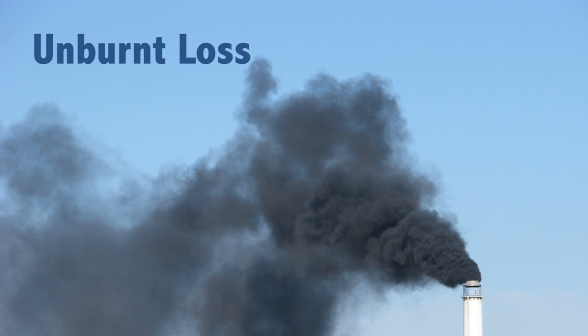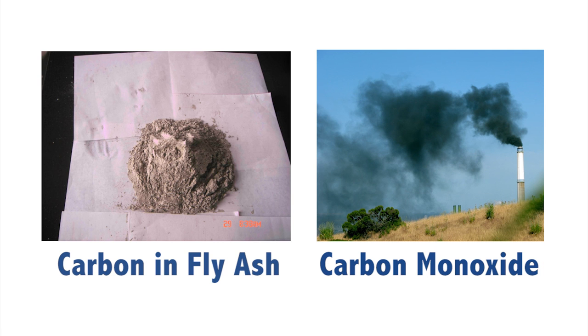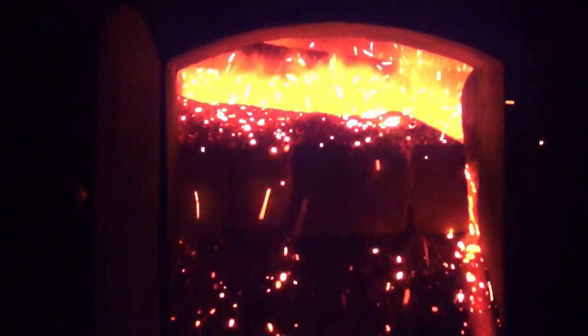Now let us look at unburnt losses. Unburnt losses are the losses that happen due to the carbon in the fuel not getting properly burned, which means the carbon comes out of the boiler either in the form of carbon in fly ash or in the form of carbon monoxide in the flue gases. If one looks at the three T's of combustion — turbulence, time, and temperature — for proper combustion there should be enough turbulence to allow proper mixing of the fuel and the air.